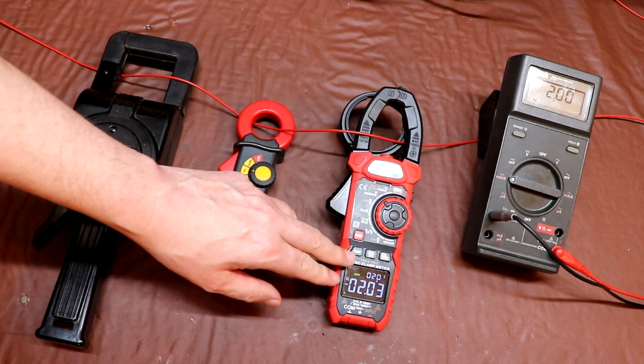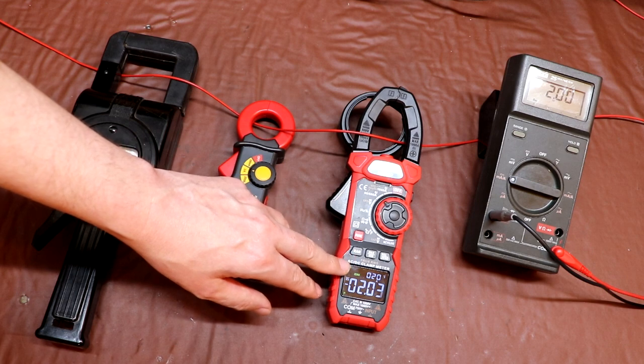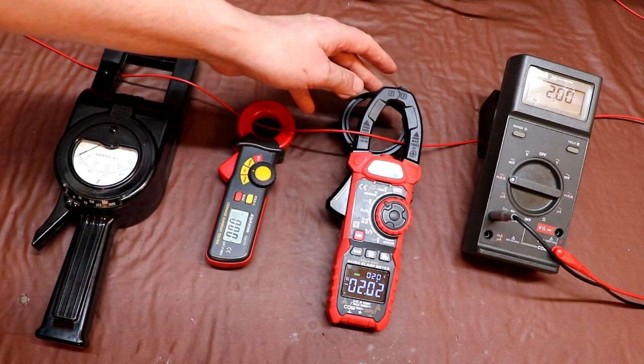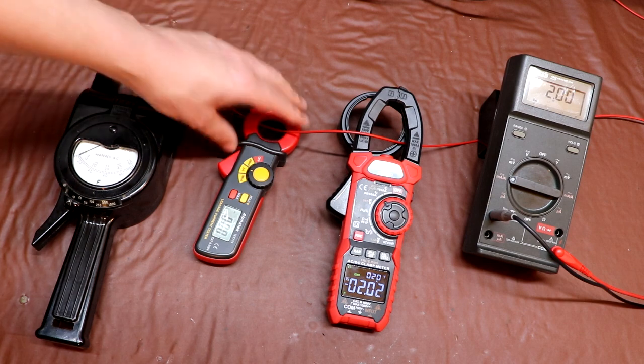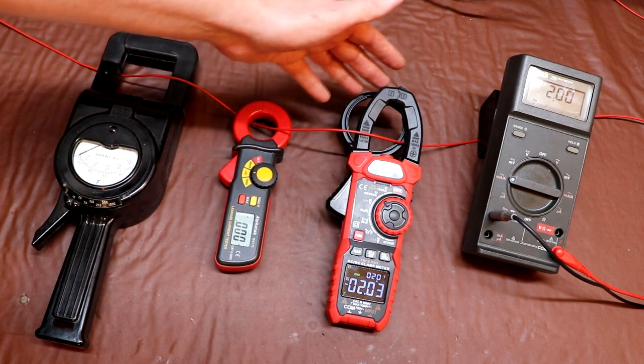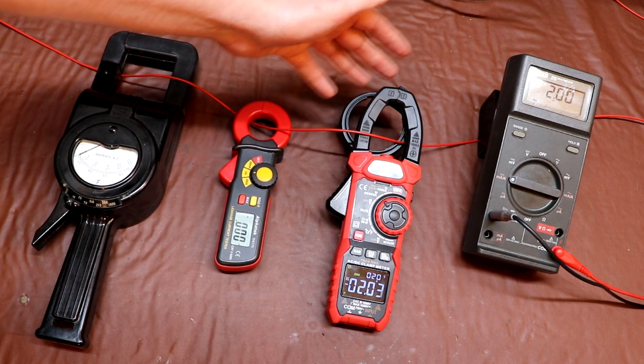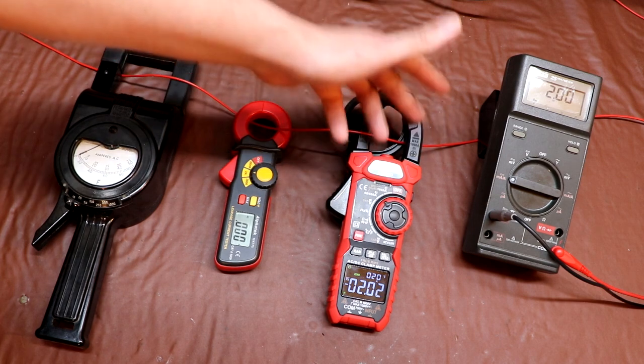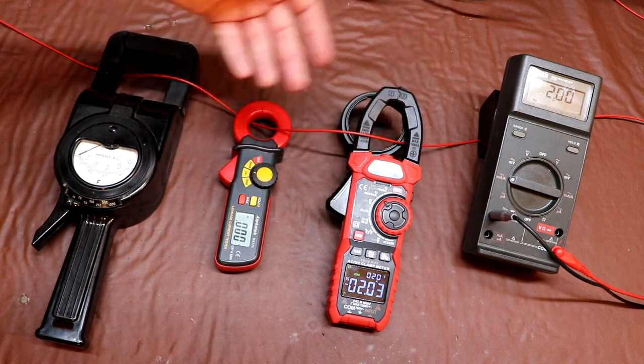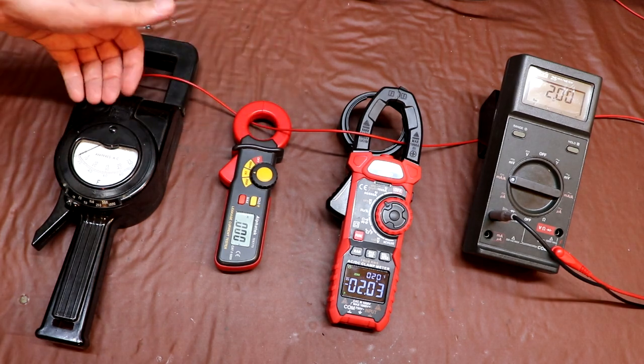Now I actually think it's quite amazing that our KAIWEETS meter here is able to give a DC current measurement when our other two meters here aren't able to do that. Of course, the reason that it can do that is because the sensing technology built into the clamp here is quite different than the one employed by these other two meters.